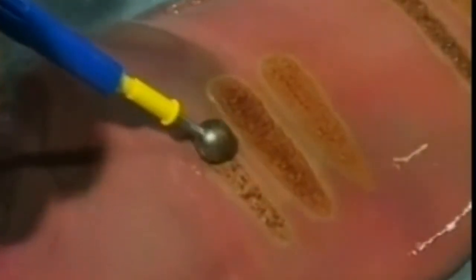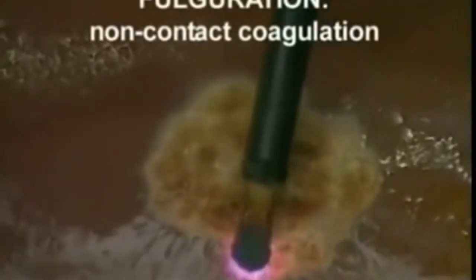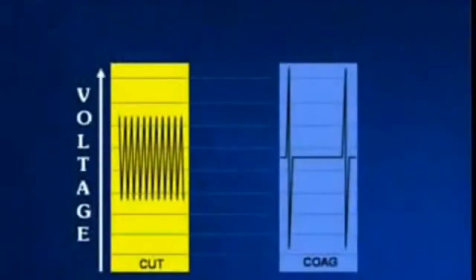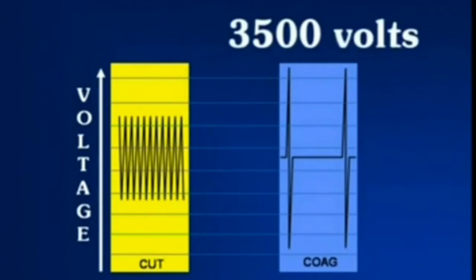Coagulation is useful where tissue is oozing and may be used to desiccate tissue where the instrument is used in direct contact with the tissue, or fulgurate where the voltage is increased, the instrument held slightly above the tissues, and the sparks allowed to jump across the gap. Another important fact to be aware of is that coagulative currents can be associated with peak voltages from around 3500 to as high as 9000 volts.